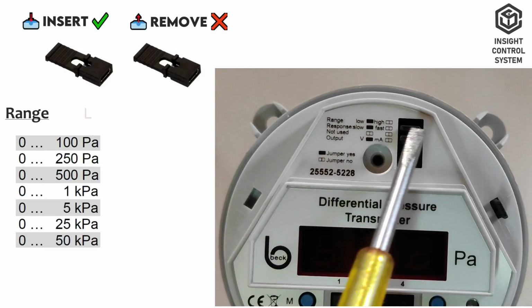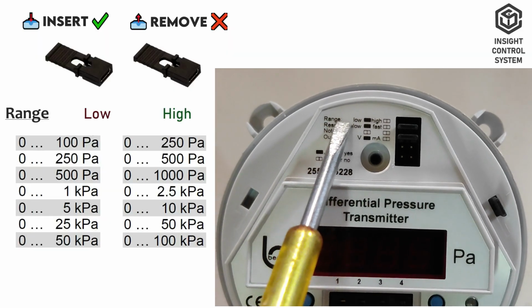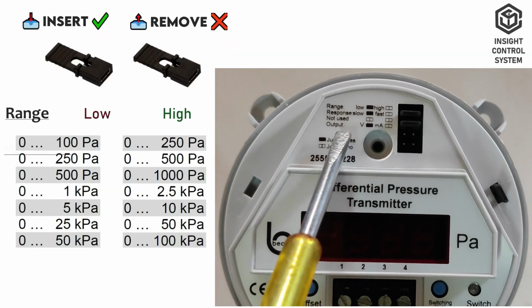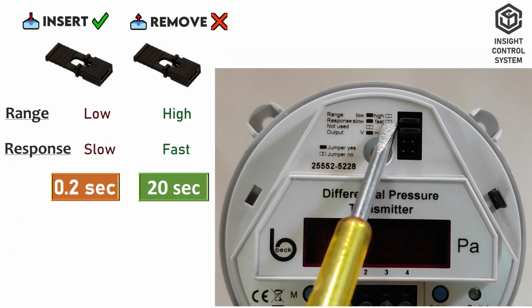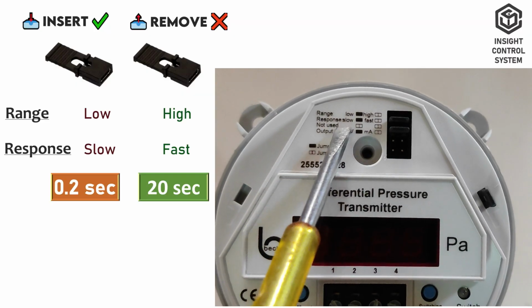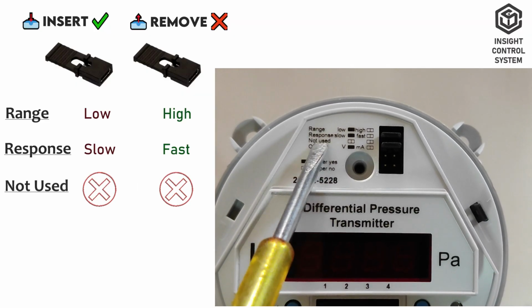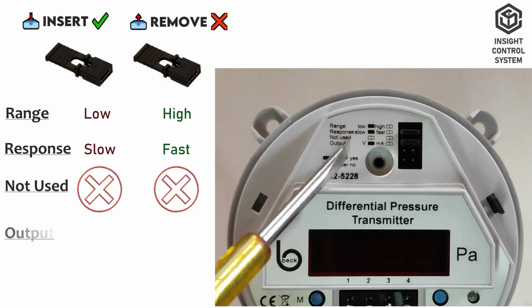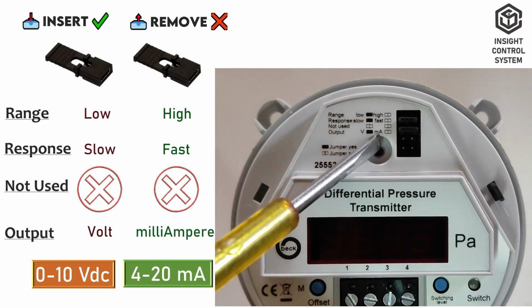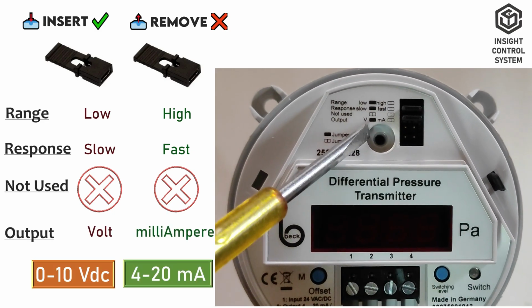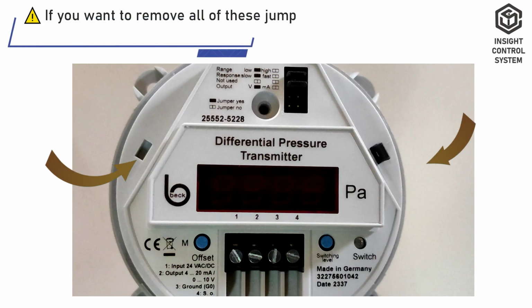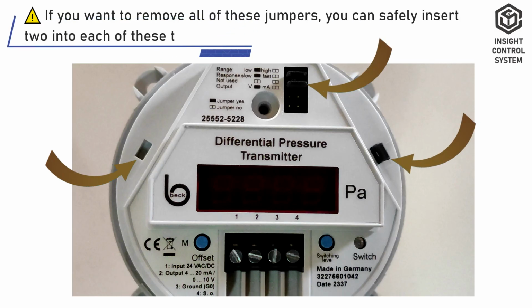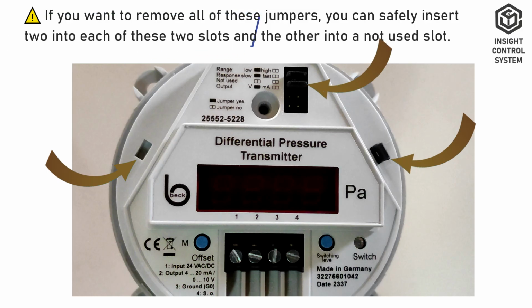The first jumper slot specifies whether the measurement range is low or high. The second jumper slot indicates whether response times are slow or fast. The third jumper slot is not used. The fourth jumper slot represents the output signal voltage or current. If you want to remove all of these jumpers, you can safely insert 2 into each of these 2 slots and the other into a not used slot.